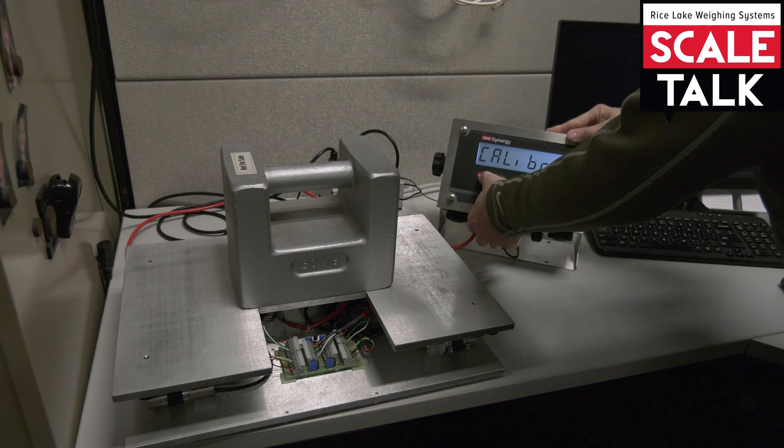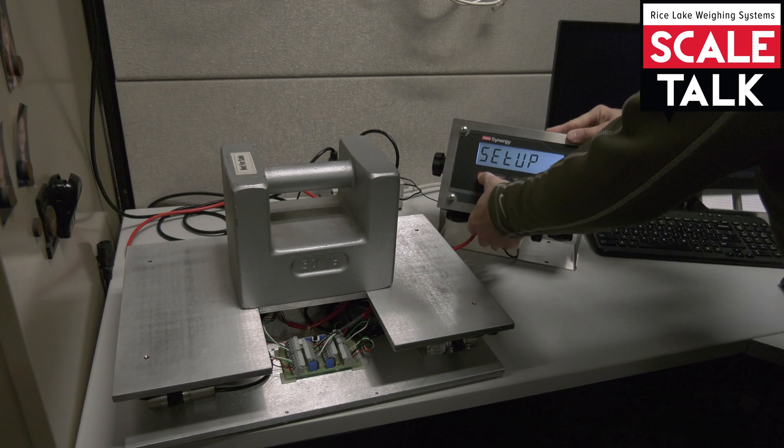Then I'll exit by going back up to setup and pressing that zero key one last time where it will save and exit. And hopefully we have 50 pounds. There we go. The scale is now set up as a 50 pound scale and properly calibrated.